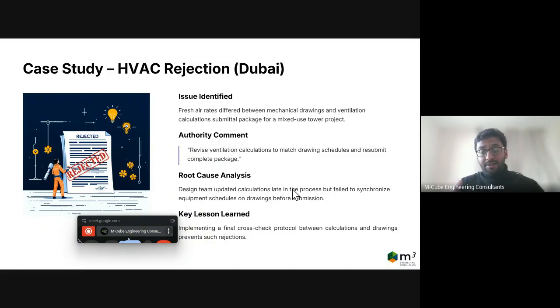Another important reason for rejection of HVAC fresh air calculation is when your riser diagram is not matching your drawings and floor plans, and there is a discrepancy between the drawings, floor plans, and calculation. Ensure all three are aligned. For example, if you are showing 350 liters per second on the drawing, ensure the same is shown on your riser diagram as well as the calculation.